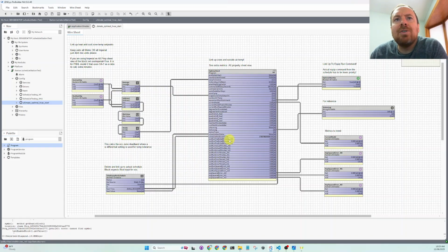So model 0 is actually the linear model, degrees per minute. Model 1 is the quadratic regression, based on the zone recovery data of the zone temperature data. And model 2 is basically model 0, linear degrees per minute, but also including the ratio to factor in weather.